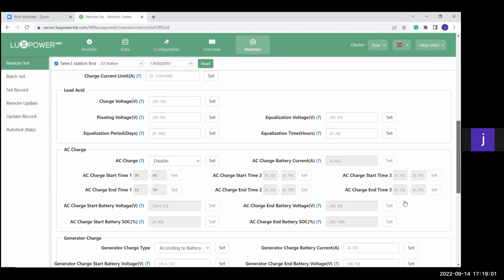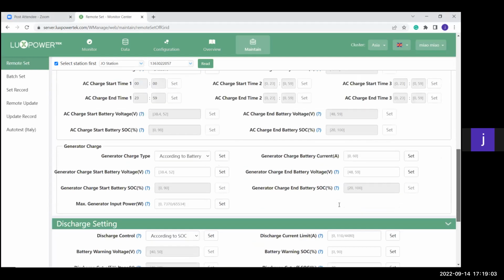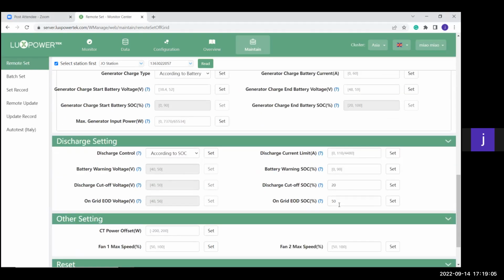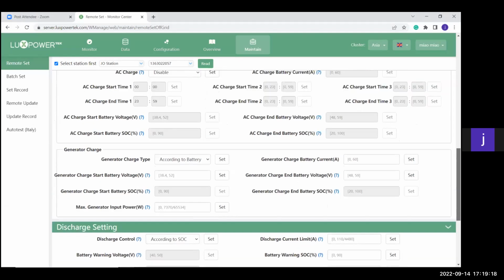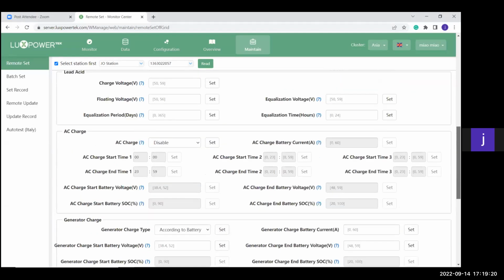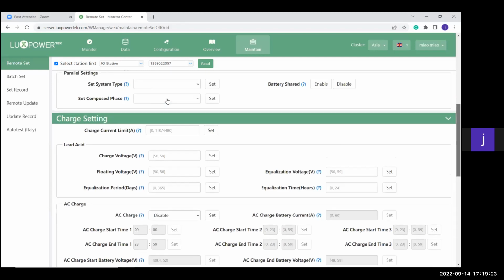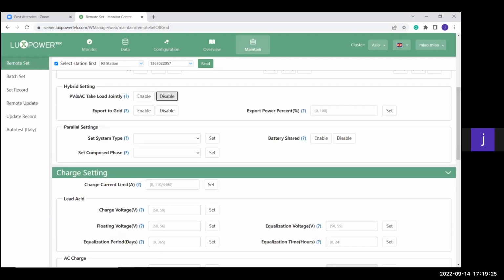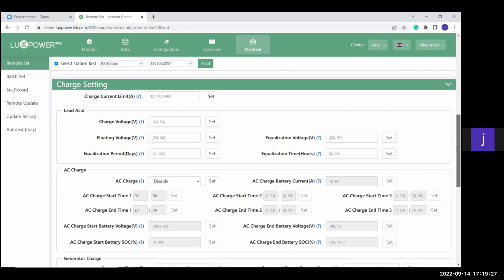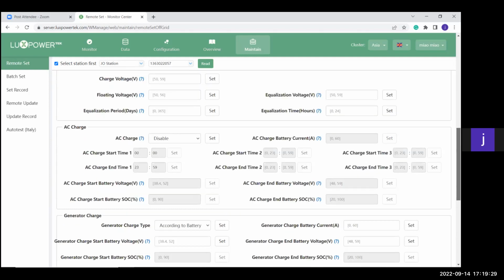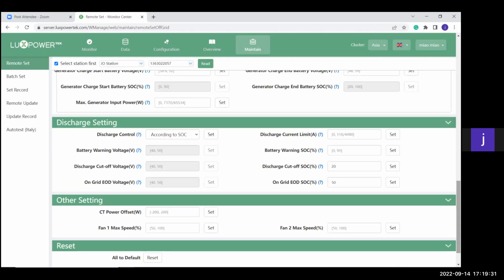have this value set here, your on-grid EOD. So let's say your batteries were drained to 50%. The panel power will be prioritized to charge your batteries first up to 60%, and then it will start to use battery power again for certain functions. So if you want your panel power to firstly charge your batteries, you're going to have to have this one disabled here, and then it will automatically charge your batteries and then provide to the loads.